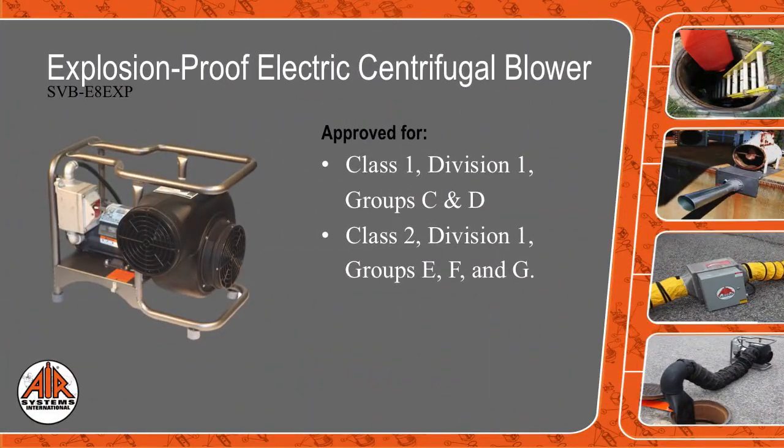The explosion-proof electric centrifugal blower is approved for use in the National Electrical Codes, NECs, Class 1, Division 1, Groups C and D, Class 2, Division 1, Groups E, F, and G. It is important to ensure that all electrical equipment use and installation comply with the NEC codes.